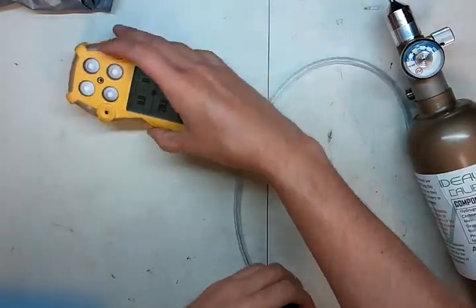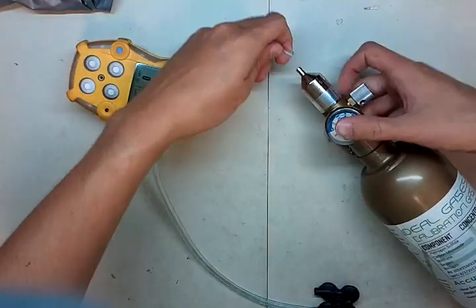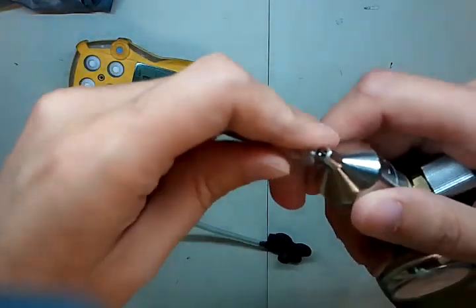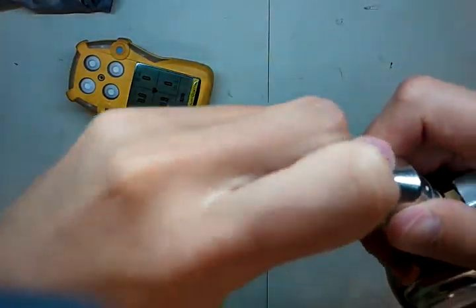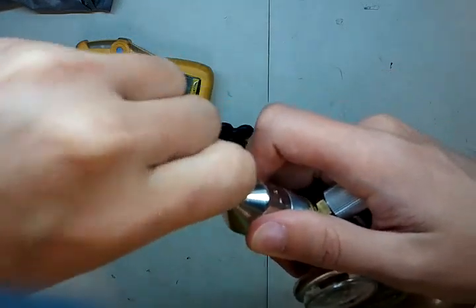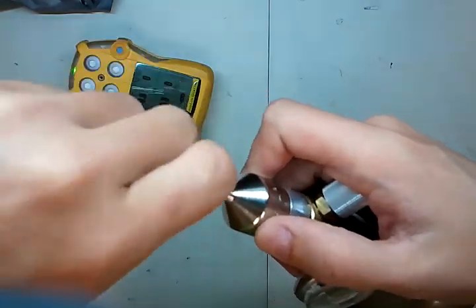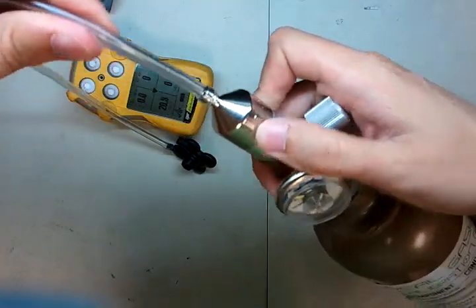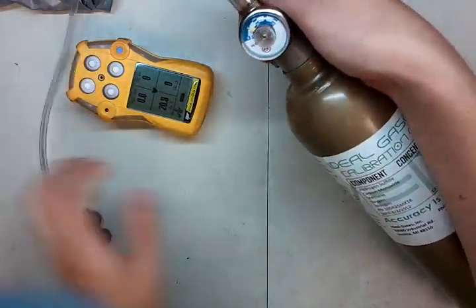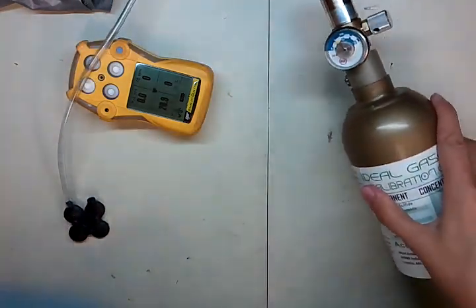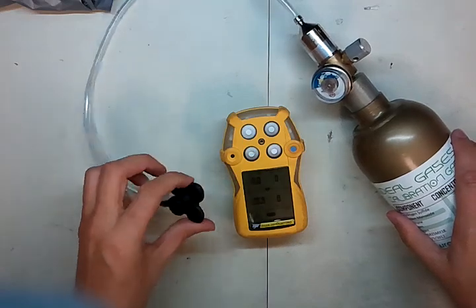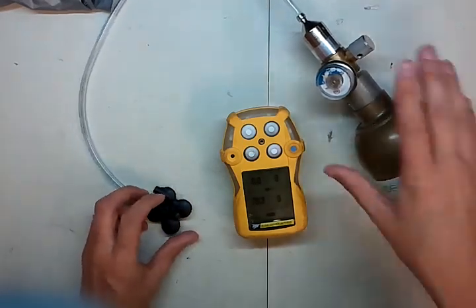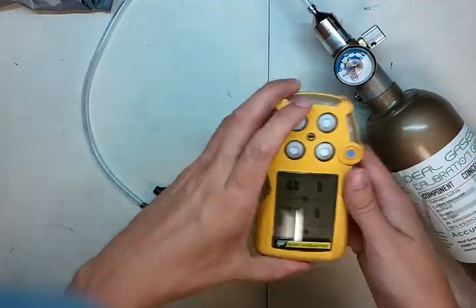And next step, put the tubing on your regulator. Now the tubing for the BWs is always a pain. It's really hard to get on there. It's like a really small tube. There you go. So getting it on your hose barb adapter isn't easy, but it's one of the reasons you do this before you put the monitor in calibration mode. Okay, so now we got everything prepared. We got our calibration gas, we got our calibration adapter, the regulator in. We're going to put the monitor into cal mode.